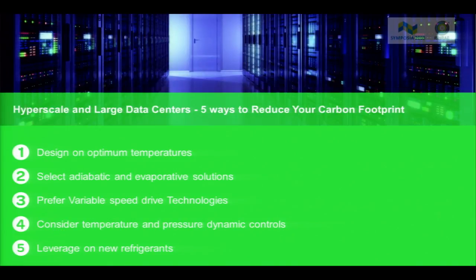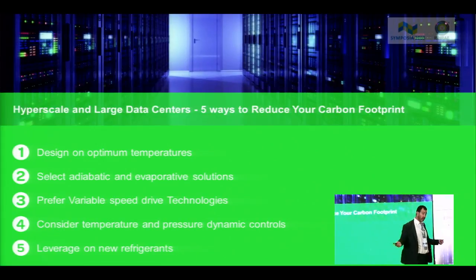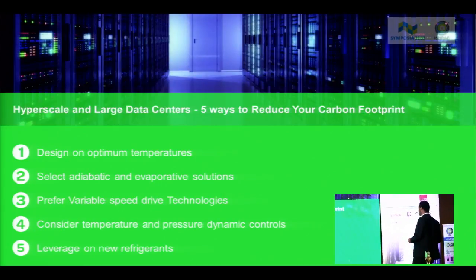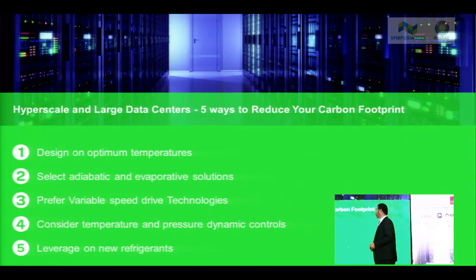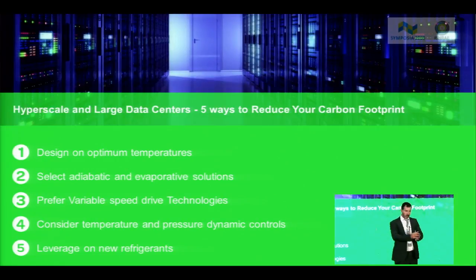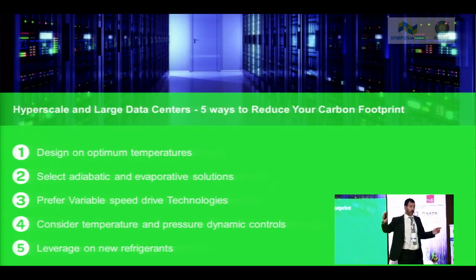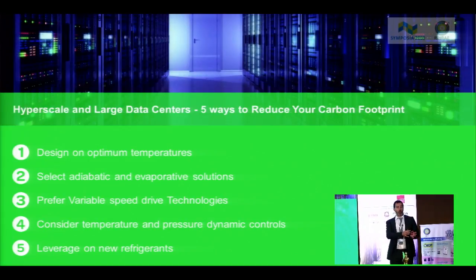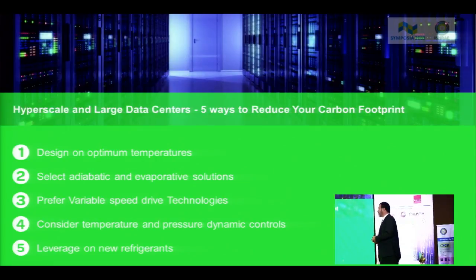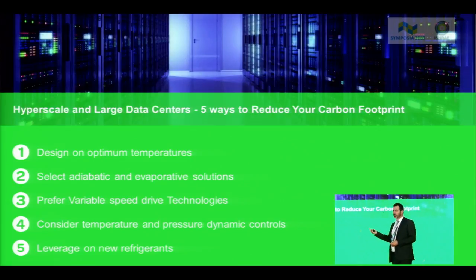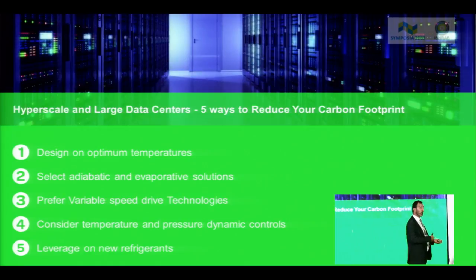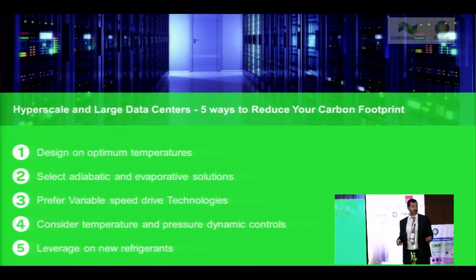What we should try is to find some general rules that help us identify the biggest and most interesting points that can help us improve the energy consumption, the energy saving. So, look at the temperature for sure, check if it is possible to use adiabatic or evaporative solutions. Pay attention to the water consumption, of course. Consider which kind of compressor to use. Evaluate the data center not at day one only, but over the entire life of the data center. So look not at the design at day one, but at how the data center can be readapted. And last but not least, look at how the new refrigerant can be not only a pain in the ass, but also an opportunity to improve the data center efficiency.